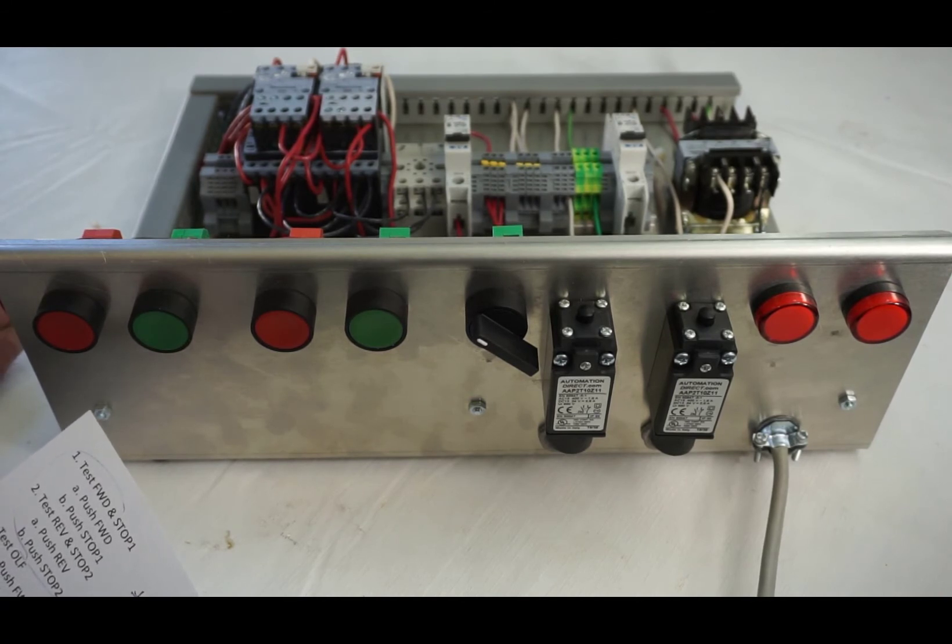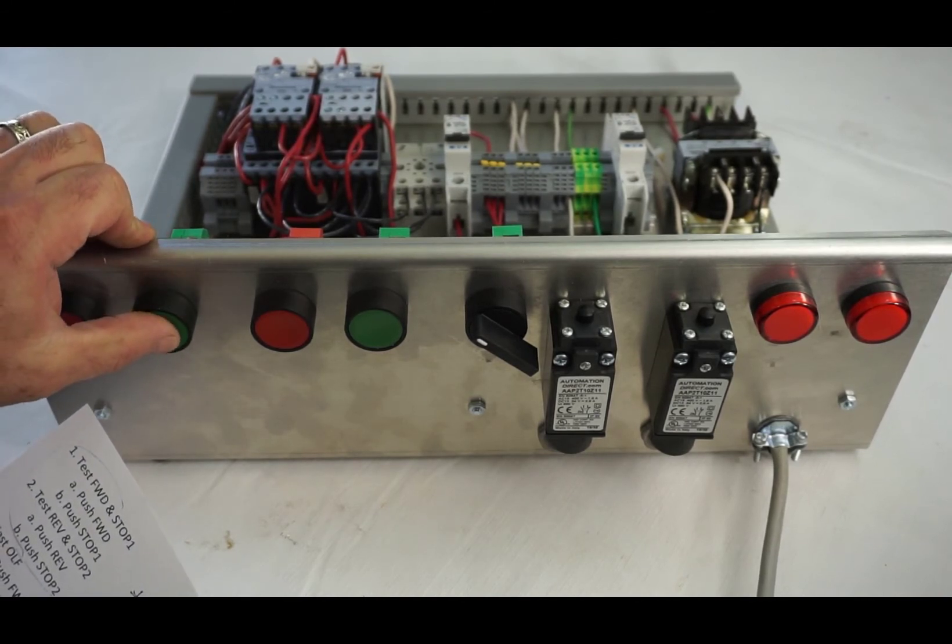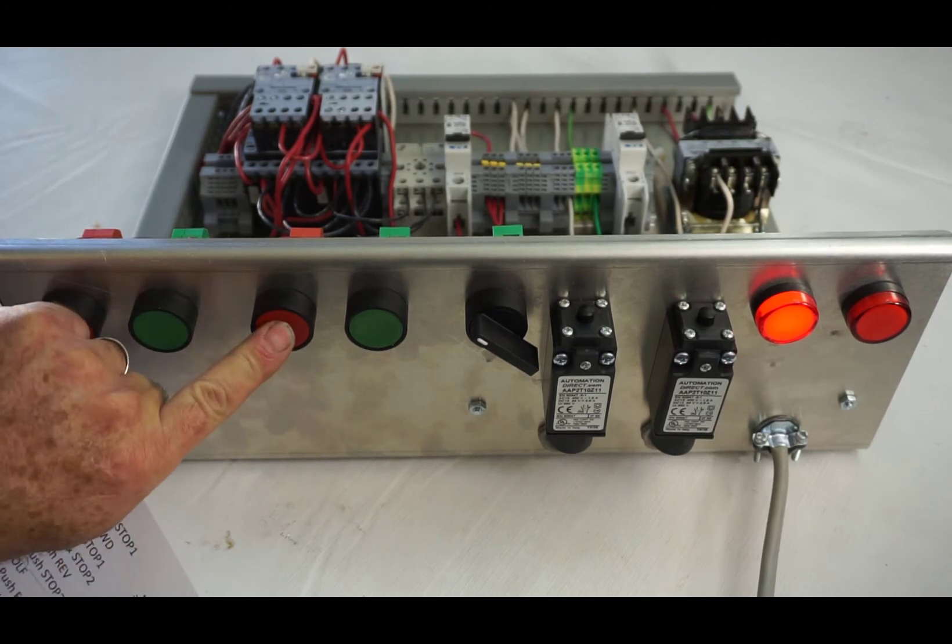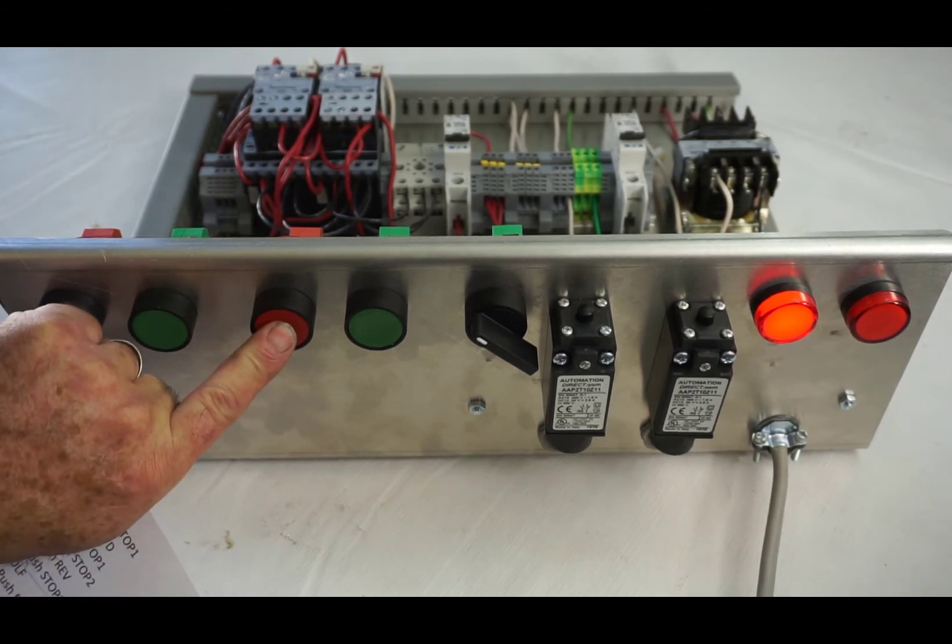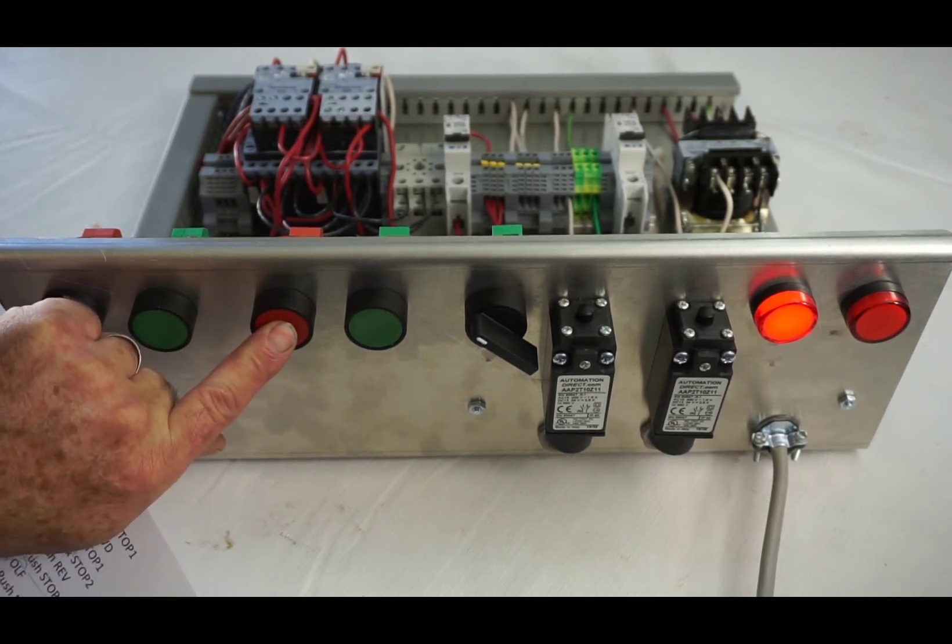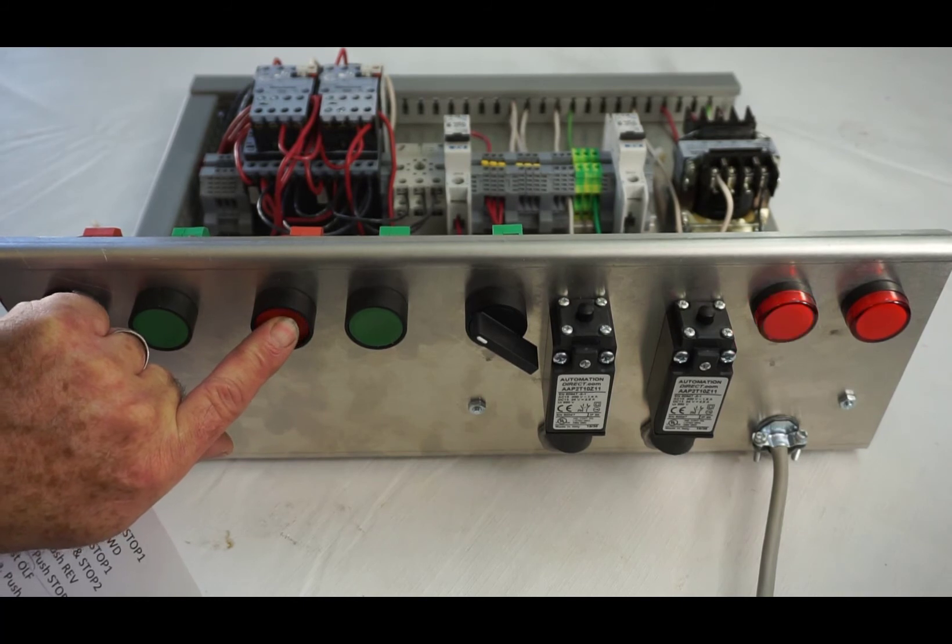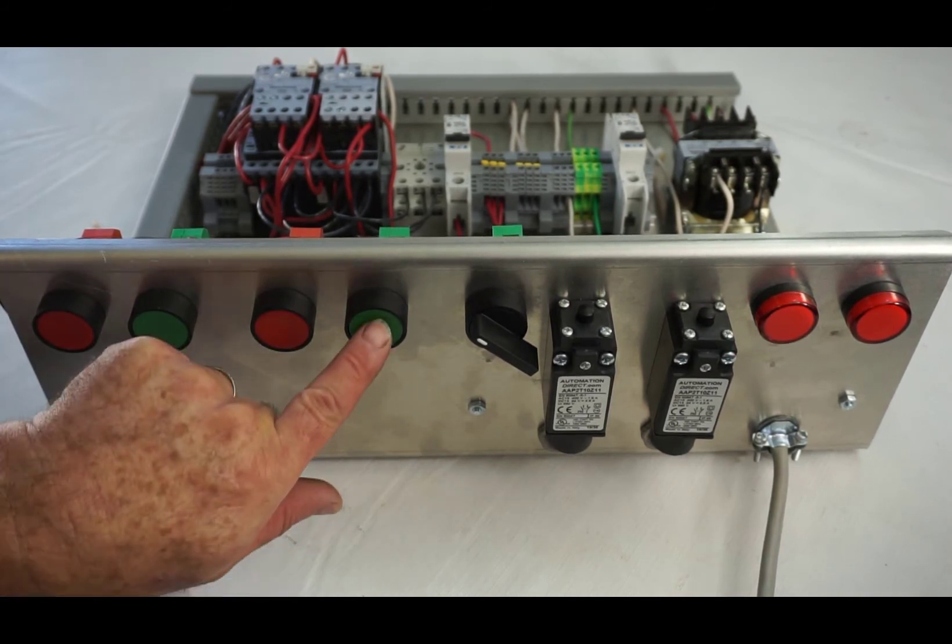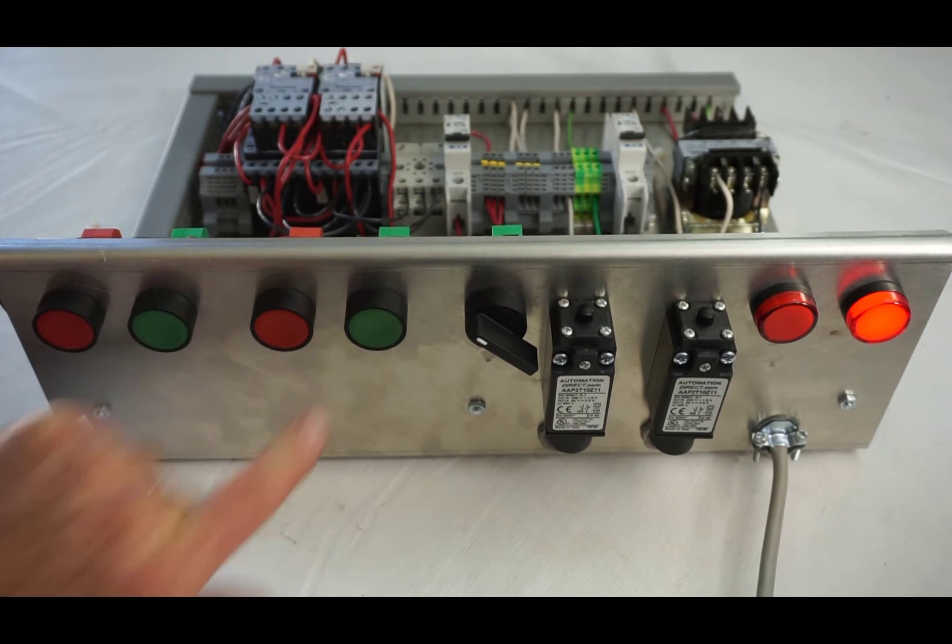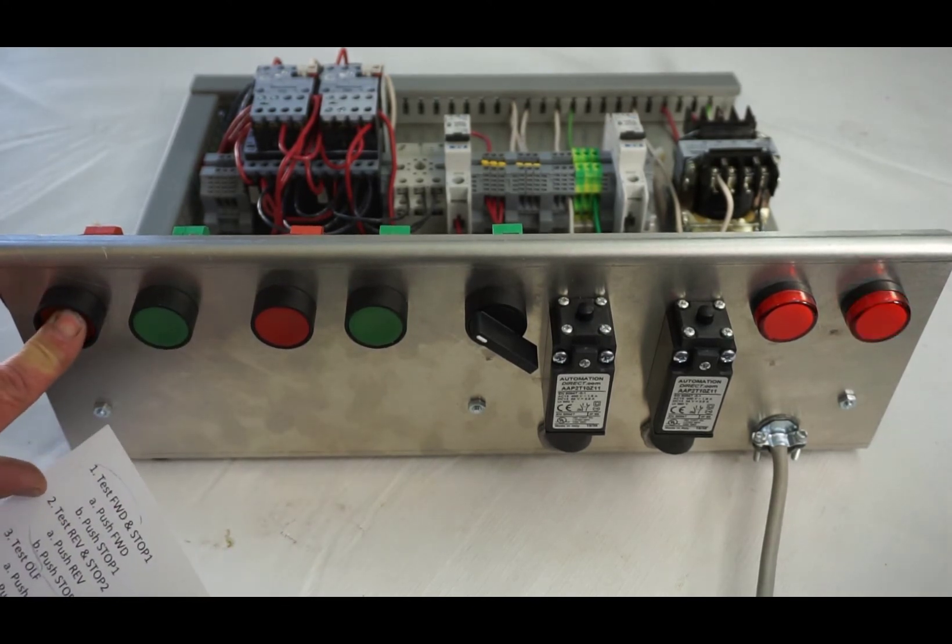Now one more thing. We want to push the forward and now push stop two to make sure both of your stop buttons are wired in series. That's good. And if you want to throw in an additional reverse and stop one.